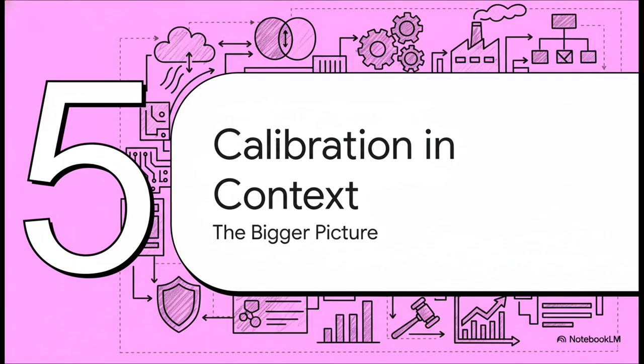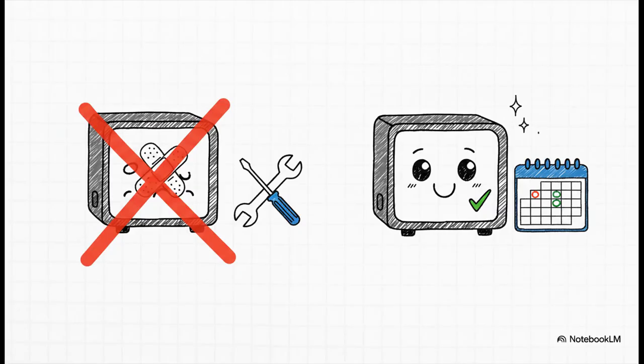All right, let's zoom out for a second. This whole calibration process doesn't just happen in a bubble. It's a really important piece of a much larger strategy for keeping your instrument healthy and your data pristine for the long haul. And if you take just one thing away from all this, let it be this. Calibration is not a one-and-done kind of deal. Think of it like a regular health checkup for your analyzer. It's something you do routinely to make sure your data is always on point.